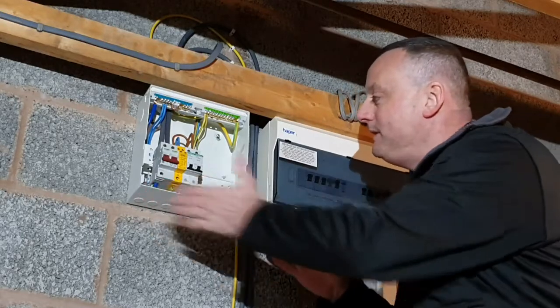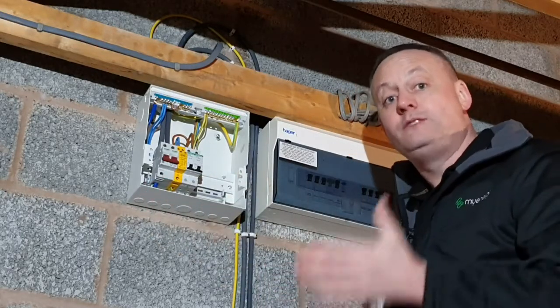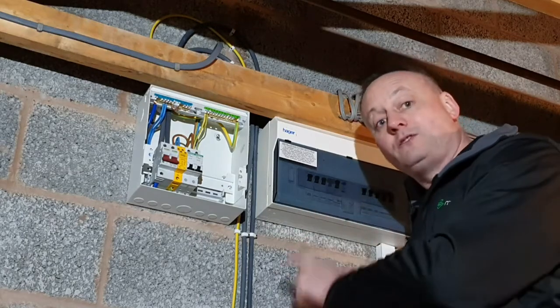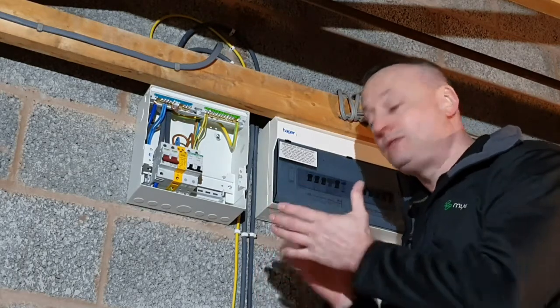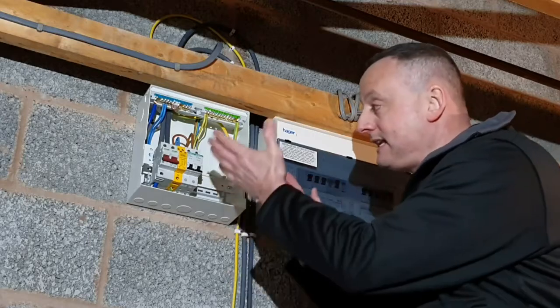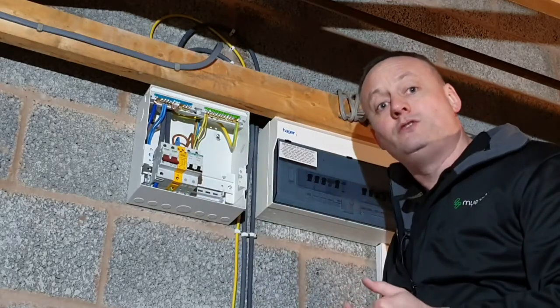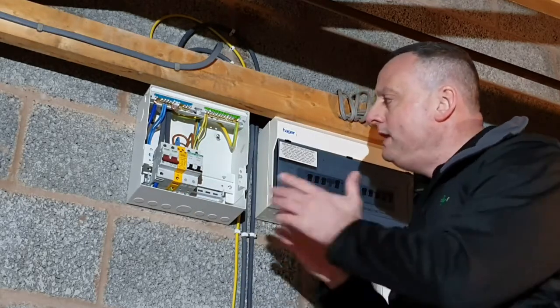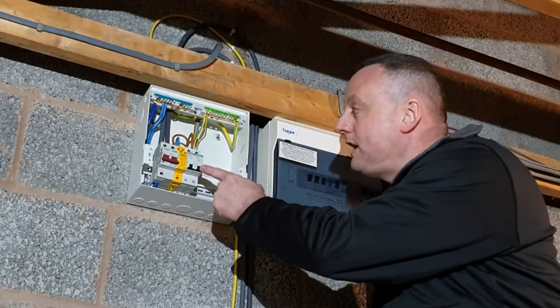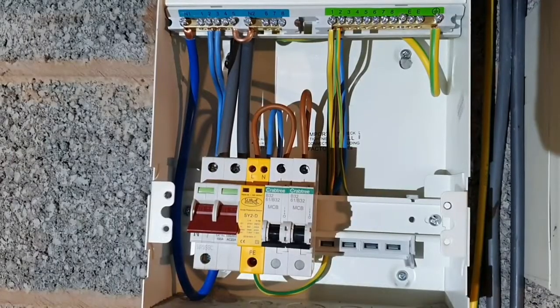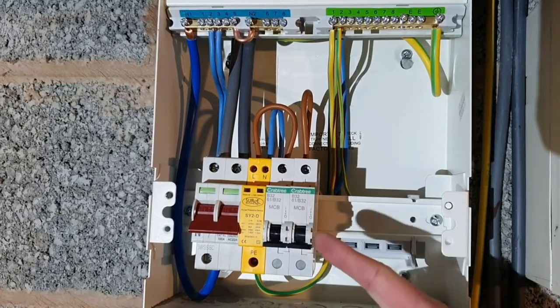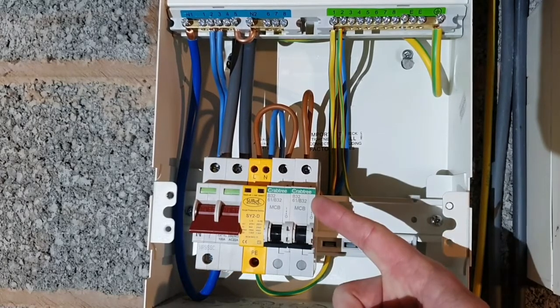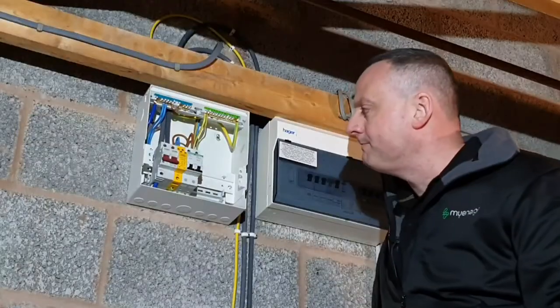So we're looking at the consumer unit itself that's been installed for the new Zappi 2 EV charging point. We saw outside how we split the tails. We've got a set of tails now feeding the main consumer unit, and a set of tails now feeding the actual new consumer unit for the Zappi 2. We look inside here, and I can see the new circuit, 6mm squared cable, twin and CPC, is actually fused at 32 amp and a Type B MCB. Is that acceptable, Joe? Absolutely.